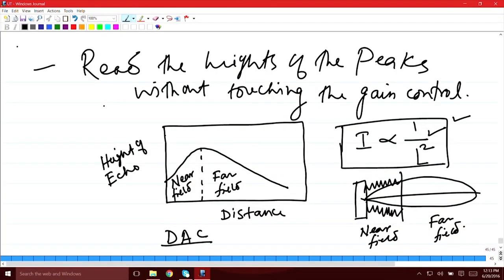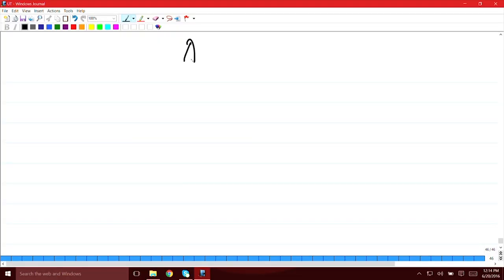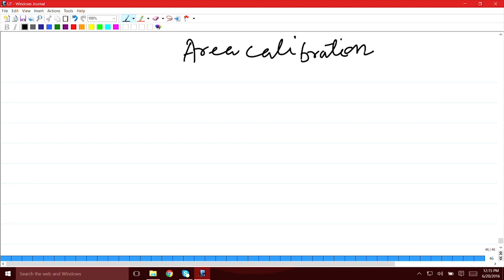Now let us see how area calibration is done. We can use the same blocks, but to calibrate for area you keep the metal distance fixed and vary the size of the hole. For blocks used in area calibration, a single number is given — 1, 2, 3, 4, 5, and so on — according to the size of the hole.